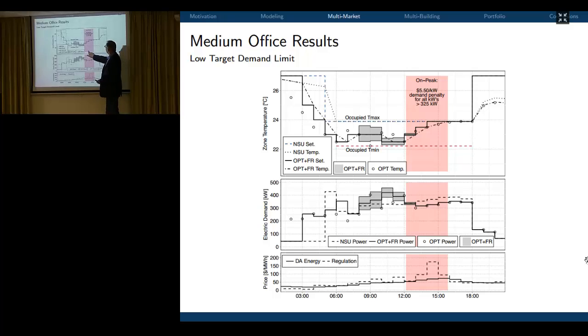Well, the answer is during this period I have to deal with this target demand limit. I cannot exceed that limit over 325 kW. So if I wanted to provide some frequency regulation, I would have to keep the set point lower, like here, to go up and down. It has to be symmetric, remember, up and down. But if I keep the building colder, then I'm going to have a higher demand. So that necessarily means during this period, there is no chance I can provide both frequency regulation and still maintain the target demand limit. So this is when I have a low demand limit, and this is 325, and 325 is right here. So I'm basically telling the building, don't ever, during that red period, go above 325 kW.